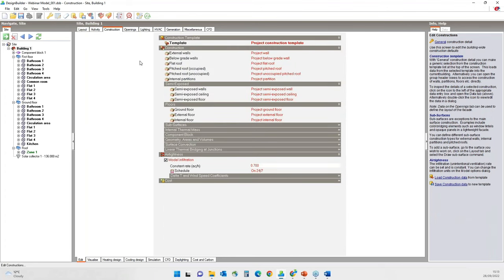Going to the constructions tab, under the air tightness header, the infiltration rate is set to a fixed value of 0.7 air changes per hour. However, the infiltration rate should be appropriate for the building age and type. You can also switch off infiltration entirely, but that should only be done with great caution as it can have a big impact on results for anything other than very airtight buildings. I will assume this is a new build and will set the value to 0.4 air changes per hour.